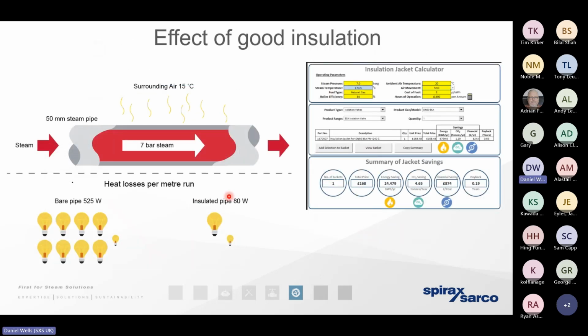Insulation's another very, very quick win. Again, something that may have been overlooked 20, 30 years ago because it wouldn't necessarily have had the payback that we were expecting. But of course, today we appreciate the cost of gas, the cost of water, the cost of chemically conditioning the water. And we appreciate that by reducing the mass of steam that the boiler needs to produce, we're also reducing those carbon emissions significantly. So if we know the variables, the pressure, the temperature, the ambient conditions, the mass of steam, the size of the pipe, for example, then we can very often provide a significant payback for different ancillaries like traps or valves just by having an upgraded insulation jacket. And that information can be provided in terms of carbon saving, in terms of energy saving, or in terms of payback.